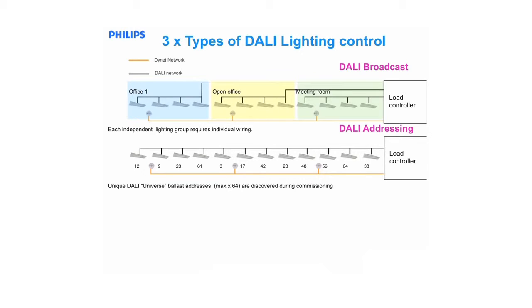Once all this information about the individual ballast addresses has been collected, then the fittings can be grouped into these useful areas. These logical areas are overlaid on the original DALI addresses, and we can see here that they achieve the exact same grouping effect as what was achieved in the DALI broadcast method. Functionally, from the end user's perspective, there is no difference in what control is provided.